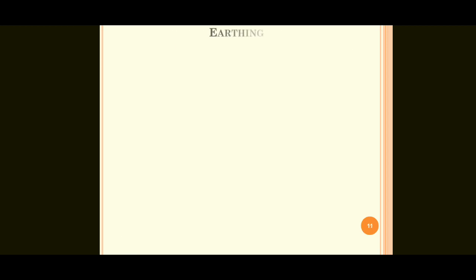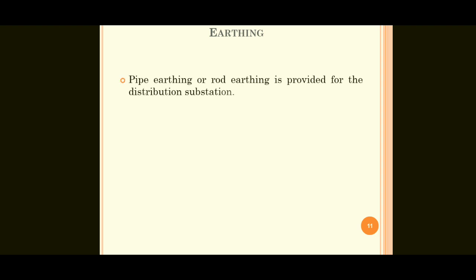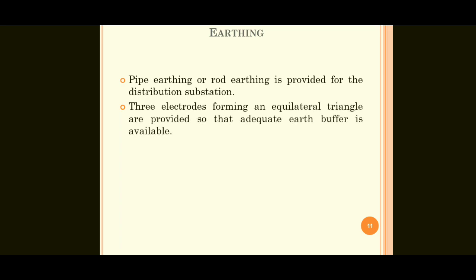Next one, earthing. Earthing I already covered in previous lectures. Earthing is of two types: pipe earthing or rod earthing, and second one, plate earthing. So for different applications, these two types are used. Depending on the application, either pipe or rod and plate earthing are used. Here, the pipe earthing or rod earthing is provided for the distribution substation. 3 electrodes forming an equilateral triangle are provided so that adequate earth buffer is available.